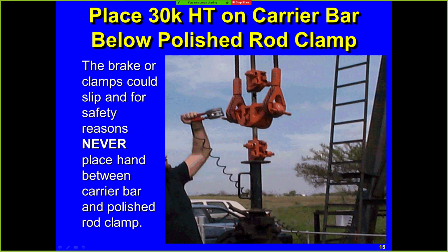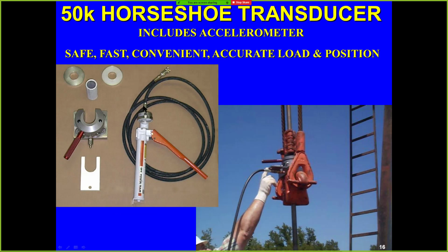But that's a quick and easy way to install a 30K load cell to measure the actual load. Now this is the 50K load cell, and it's similar to the 30K load cell, but on the bottom of it, it has a jack, and you pump hydraulic pressure through into this quick connect. You can see four holes right there, and these pistons come up and raise this load cell.